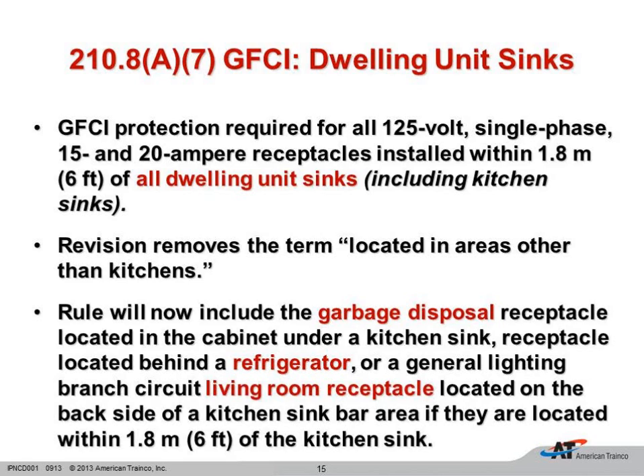And it's going to have to be readily accessible. So we're not going to be able to put a duplex GFCI behind that refrigerator. We're either going to have to protect it with another GFCI, or if we want our refrigerator on a dedicated circuit, it looks like we're going to be getting a circuit breaker GFCI. So some major impacts. You can also see that if your kitchen sink is on the same wall as another room, whether it be the dining room or the living room, and there's a receptacle right on the back side of that wall, that one is also going to have to be GFCI protected. So some changes in residential GFCIs, that's for sure.